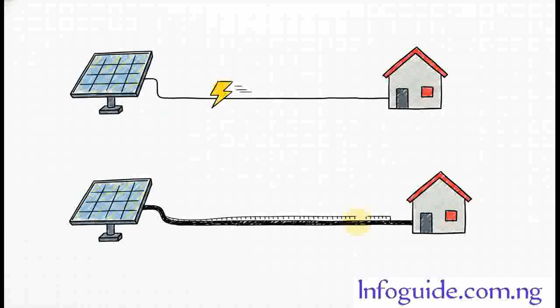All right, next up is factor number 2, distance. And this one just kind of makes sense, right? The longer that electrical road is, the more energy you're going to lose just getting from point A to point B. That's the voltage drop we were talking about. And it's why a short 5-foot cable can be much thinner than a 50-foot one, even if they're carrying the exact same current. Distance always matters.